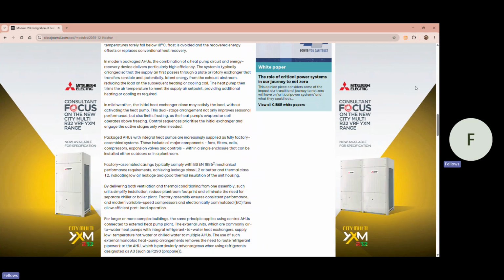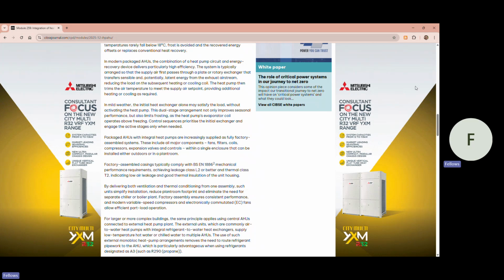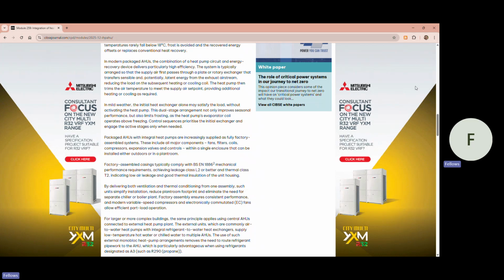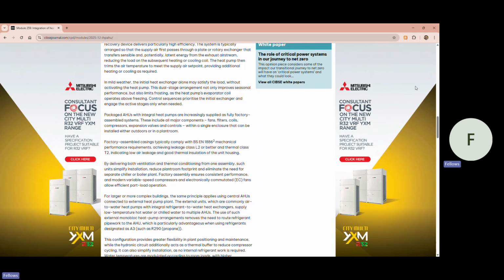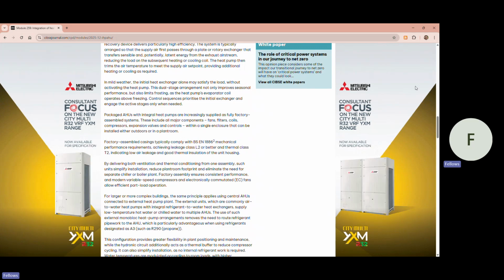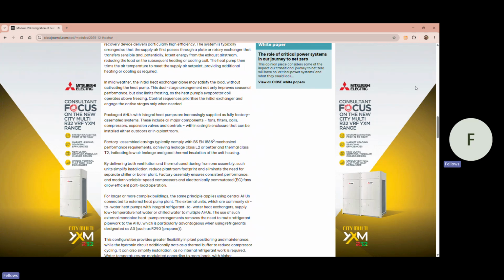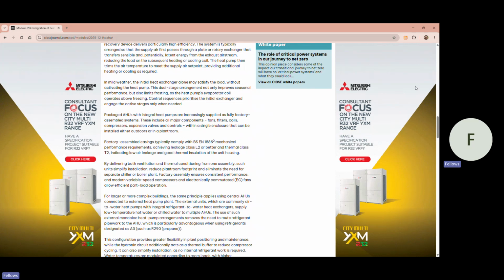These include all major components: fans, filters, coils, compressors, expansion valves, and controls, within a single enclosure that can be installed either outdoors or in a plant room. Factory-assembled casings typically comply with BS EN 1886 mechanical performance requirements, achieving leakage class L2 or better, and thermal class T2, indicating low air leakage and good thermal insulation of the unit housing.